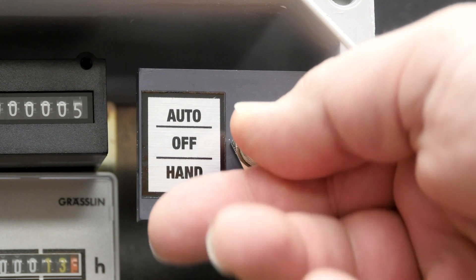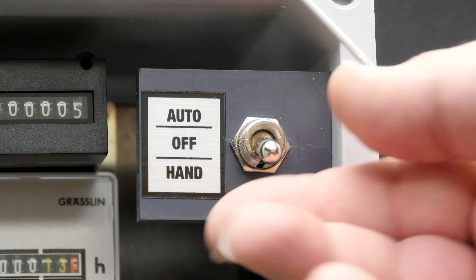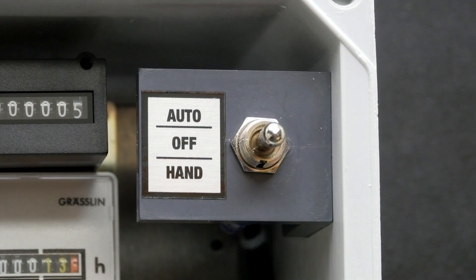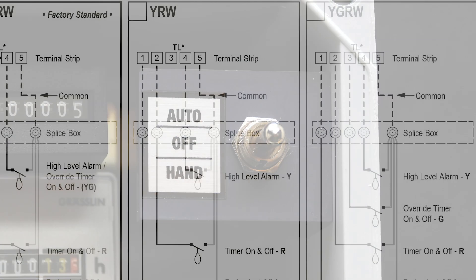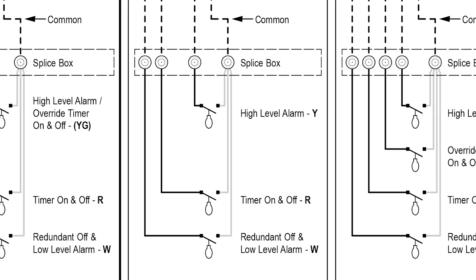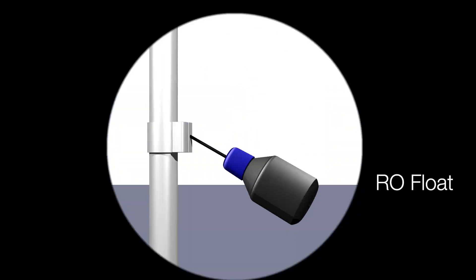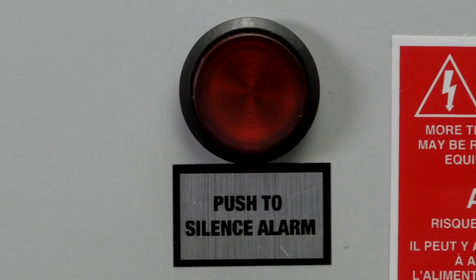The last position, manual, bypasses normal panel operation and immediately supplies power to the pump. The pump will continue to operate until the switch is moved to the off position, or the redundant off float, if applicable, drops and sounds the alarm.